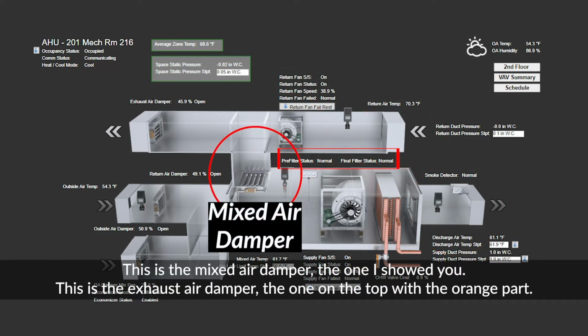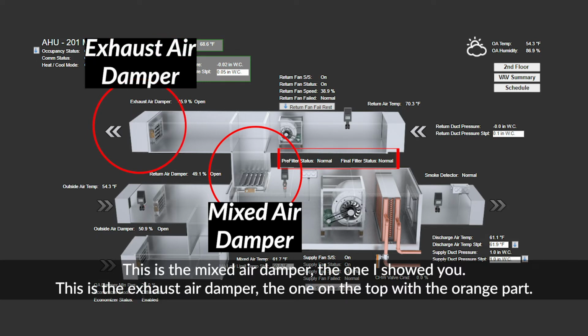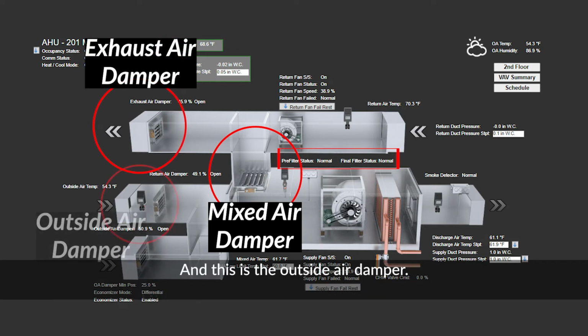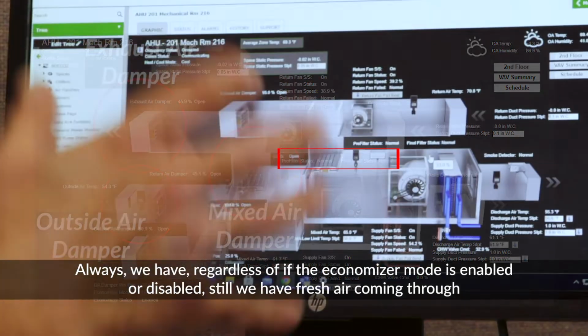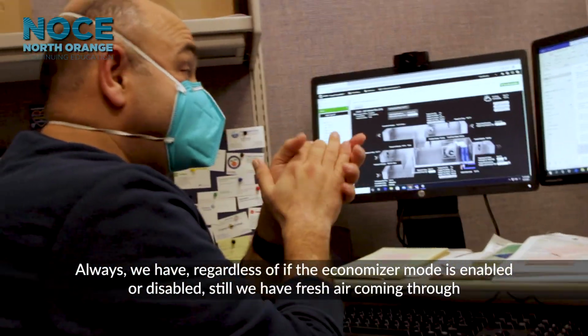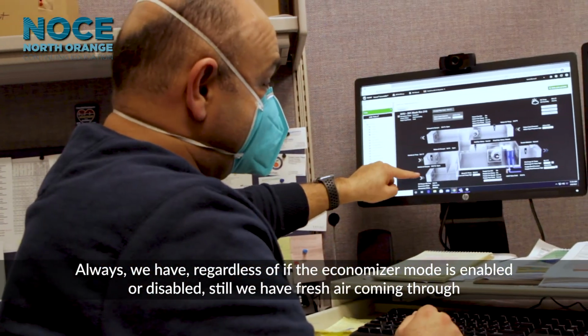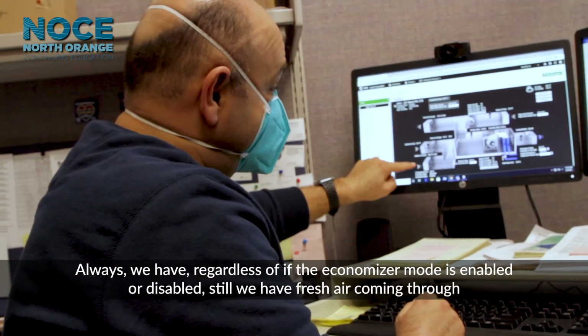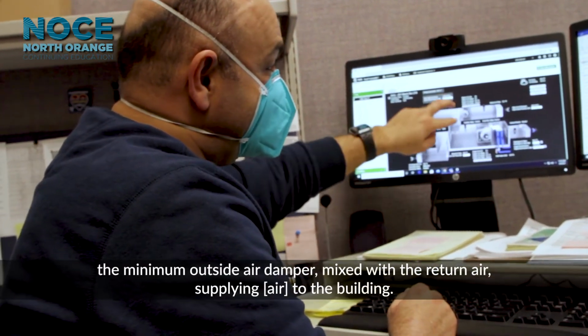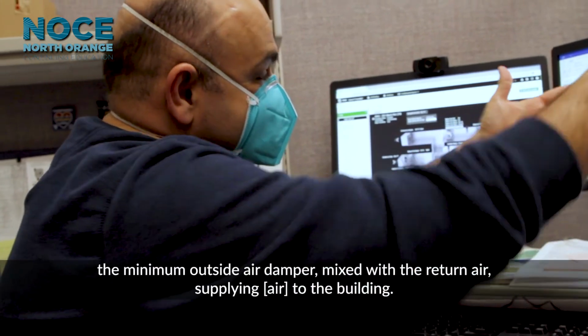So this is the mixed air damper, the one I showed you. This is the exhaust air damper, the one on the top. I showed you with the orange part. And this is the outside air damper. Always, regardless of whether the economizer mode is enabled or disabled, we still have some fresh air coming through the minimum outside air damper, mixed with the return air and supplied to the building.